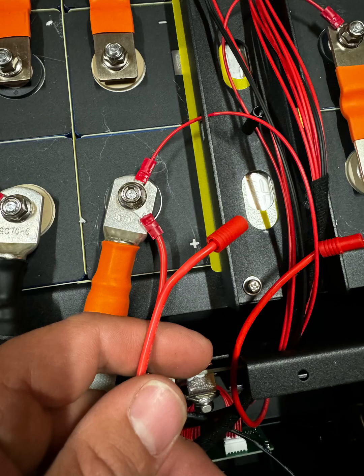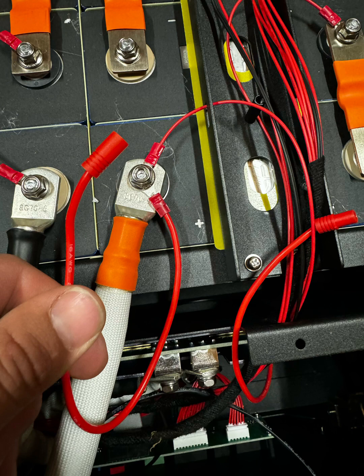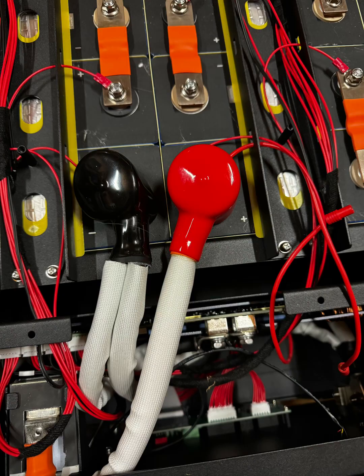It's then time to mount the main positive. You will see also here there's the red cable that goes into the BMS, which has got an open bullet connector. Leave this open just now as it's the last thing to connect the BMS before going on. I forgot to say you can also mount the covers prior to this that insulate the terminals from each other, which is certainly worth doing.